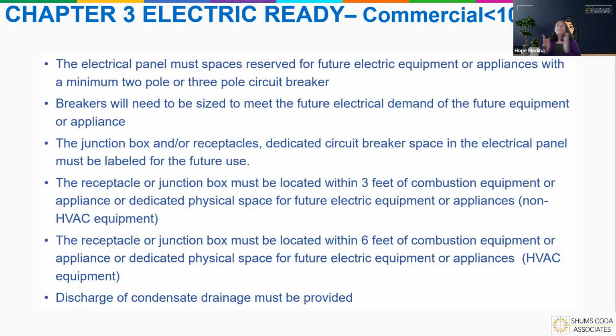If you happen to have non-HVAC equipment, like a gas stove, and you're getting a junction box ready for a potential electric stove, that receptacle or junction box has to be within 3 feet of that gas stove. And of course, it has to have the dedicated space for it, has to be labeled, and so forth.